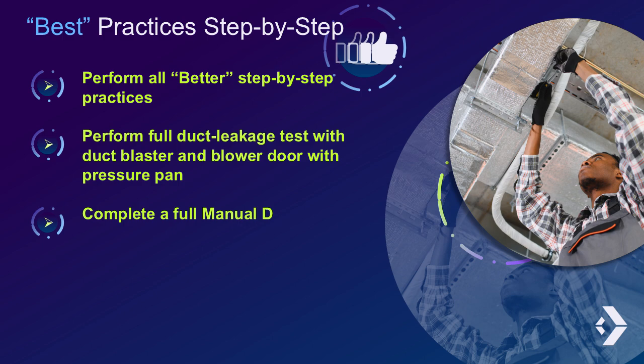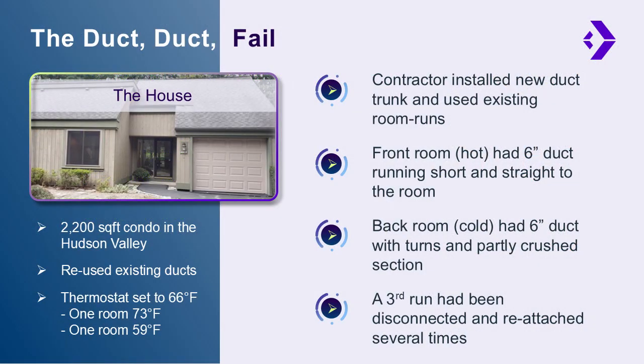consistent comfort and efficiency. Next, perform a full duct leakage test using a duct blaster and blower door with a pressure pan. This test identifies leaks in the duct system and quantifies how much air is being lost. By addressing these leaks, you can significantly improve the system's performance and prevent energy loss. These best practices ensure the heat pump can deliver the comfort and performance it's designed for, while minimizing callbacks and keeping the homeowner happy. In this example, we'll see why duct management is important.